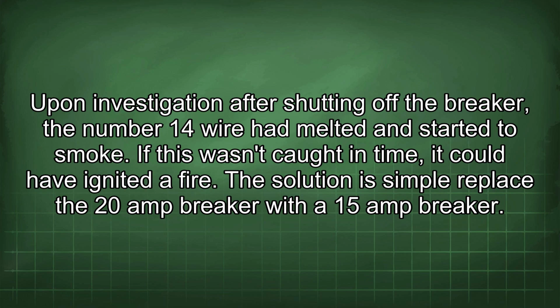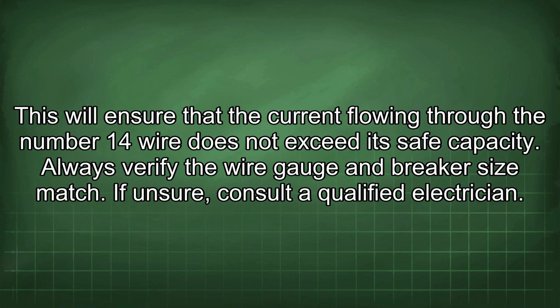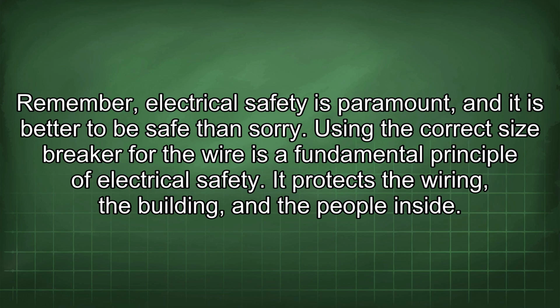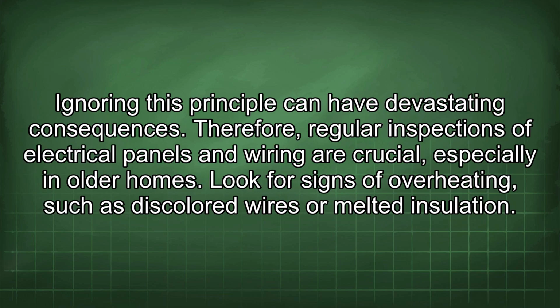The solution is simple: replace the 20 amp breaker with a 15 amp breaker. This will ensure that the current flowing through the number 14 wire does not exceed its safe capacity. Always verify the wire gauge and breaker size match. If unsure, consult a qualified electrician. Remember, electrical safety is paramount, and it is better to be safe than sorry. Using the correct size breaker for the wire is a fundamental principle of electrical safety. It protects the wiring, the building, and the people inside. Ignoring this principle can have devastating consequences.